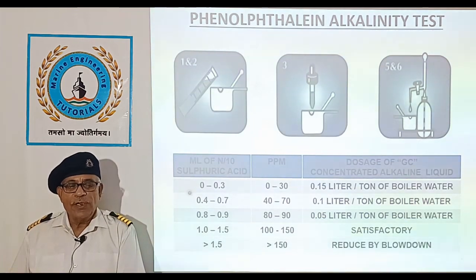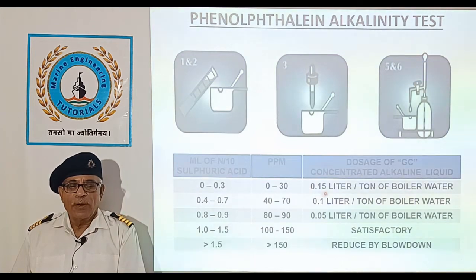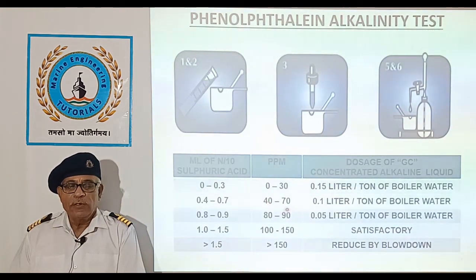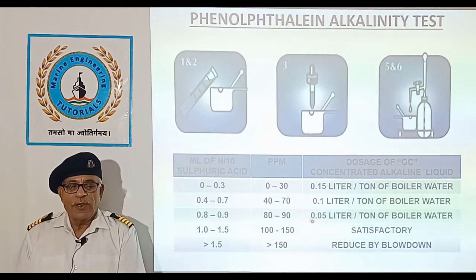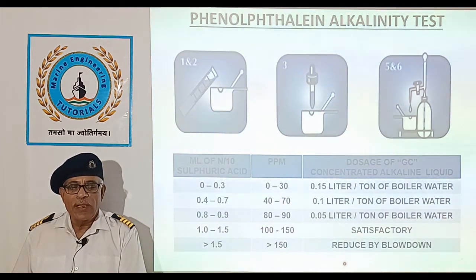If the P-alkalinity is between 0 to 30 ppm, we need to add 0.15 litre of concentrated liquid GC per ton of boiler water. If the ppm is between 40 to 70, we need to add 0.1 litre per ton of boiler water. If it is between 80 to 90, we need to add 0.05 litre per ton of boiler water. If it is between 100 to 150, it is the satisfactory range. In case it goes beyond 150, we have to reduce by blowdown.